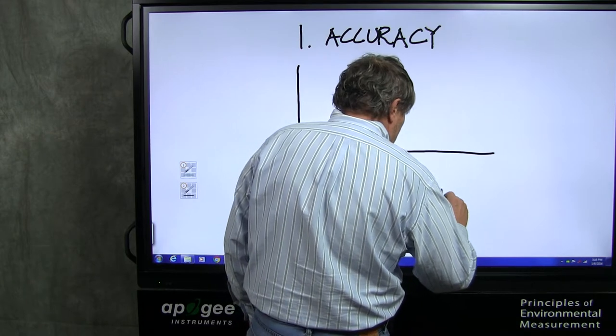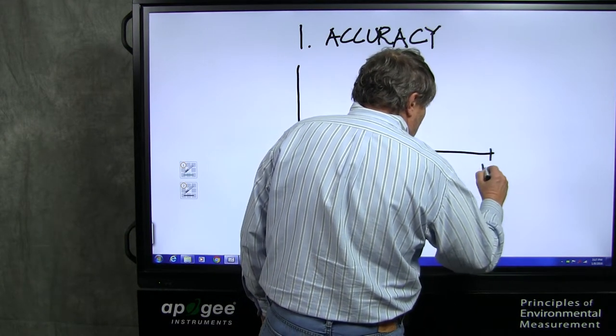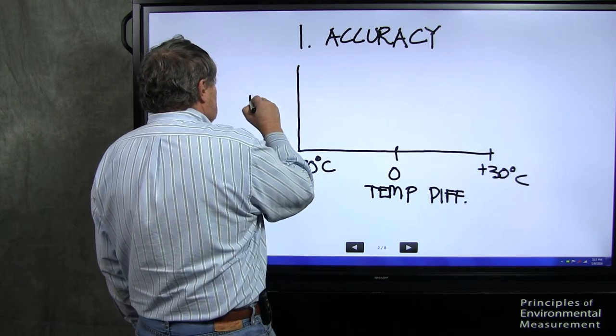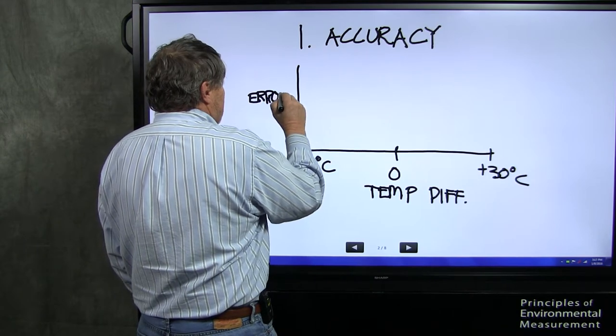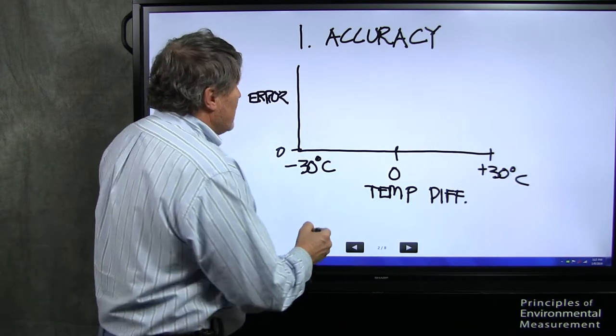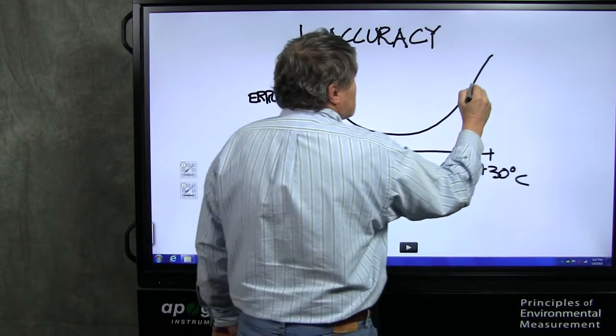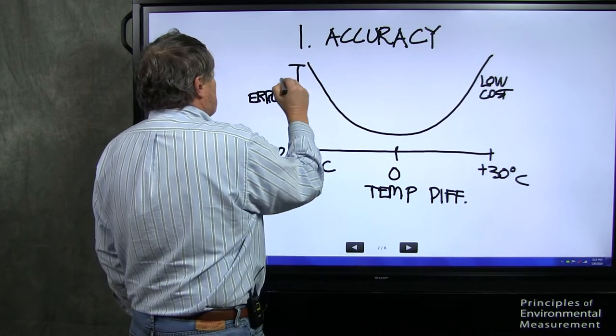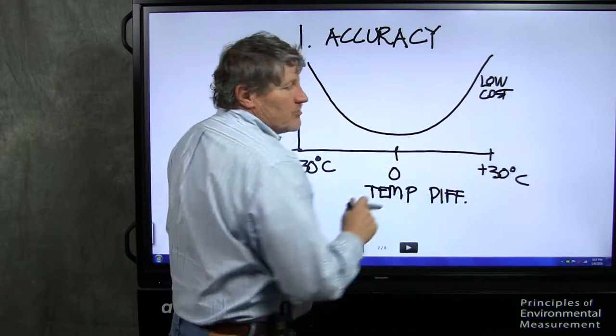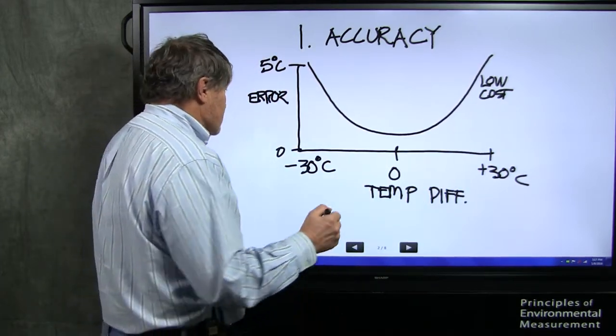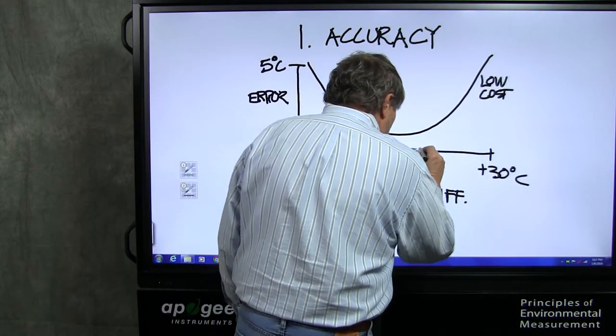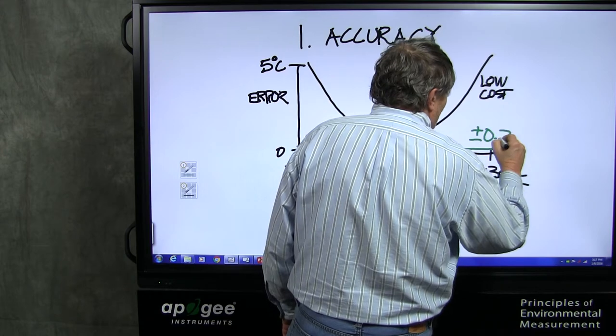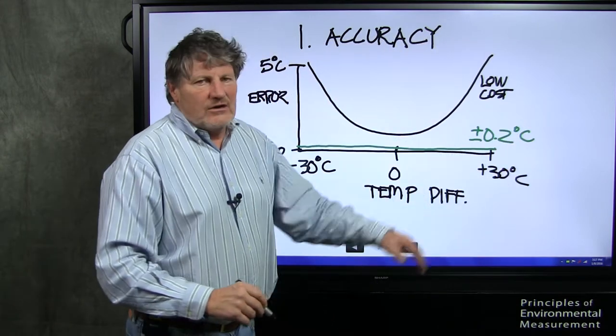So this is the temperature difference down here, temp diff. We're going to put plus 30 degrees C, and over here we're going to put minus 30 degrees C, and this is the error. So here's zero error. This is a low cost or hobby grade sensor. The error looks like that. These errors up here can be 5 degrees C as these temperatures reach the extremes. So how good is an Apogee sensor? The Apogee sensor comes in right along here. The accuracy specification for Apogee is plus or minus 0.2 degrees C, and that's over the entire temperature range.